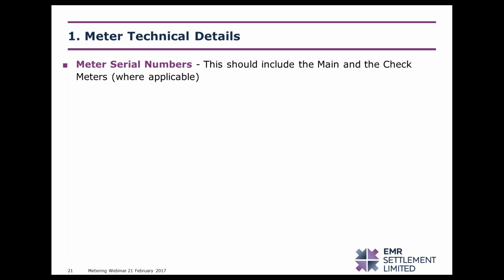You must also consider that you have to include all metering circuits in the CMU. So this can include auxiliary load circuits as part of a generating unit where net output is derived from multiple metering systems.